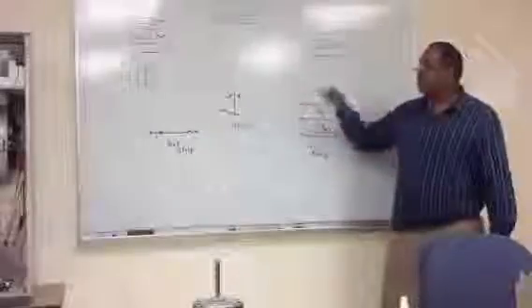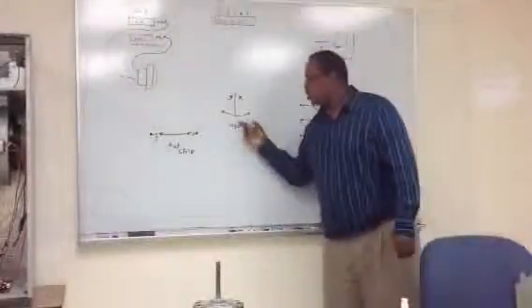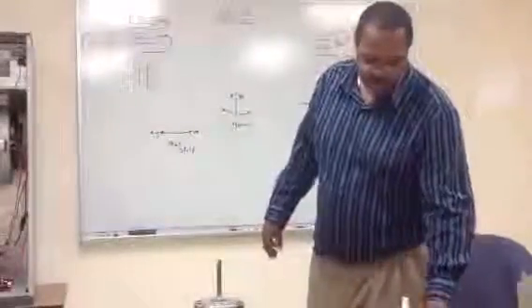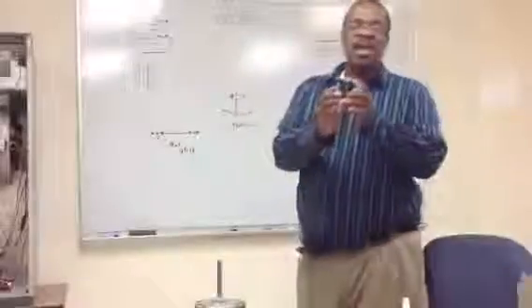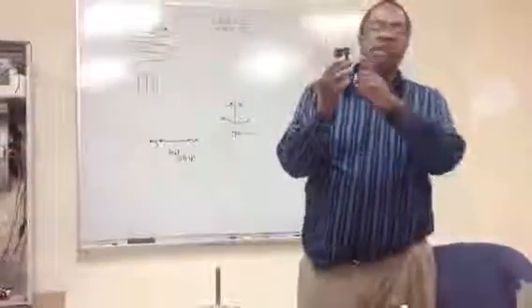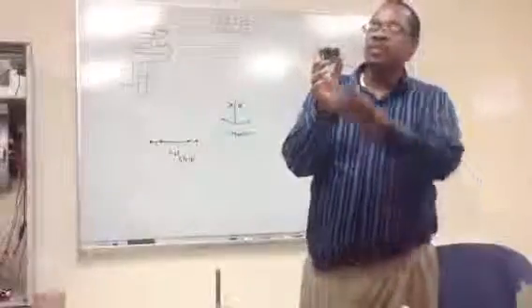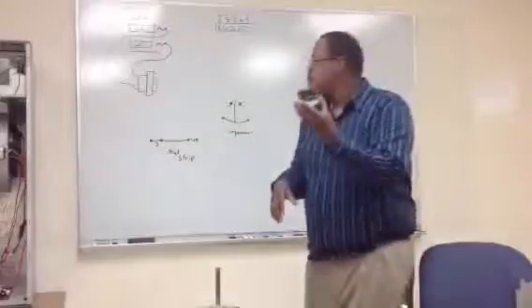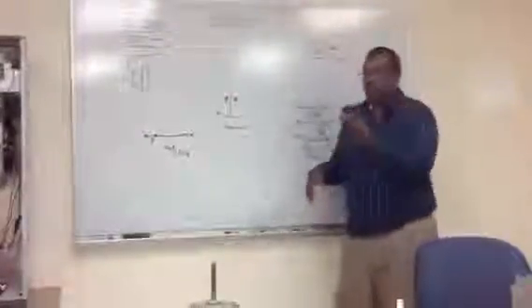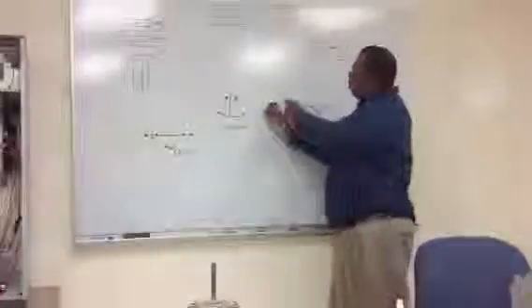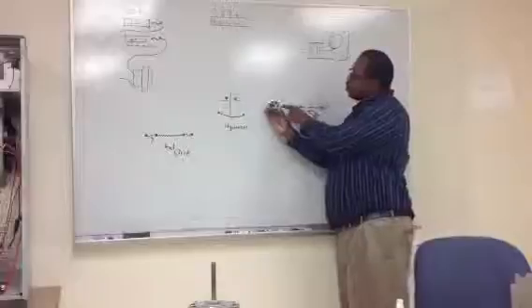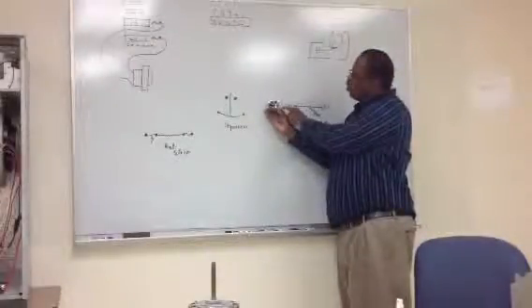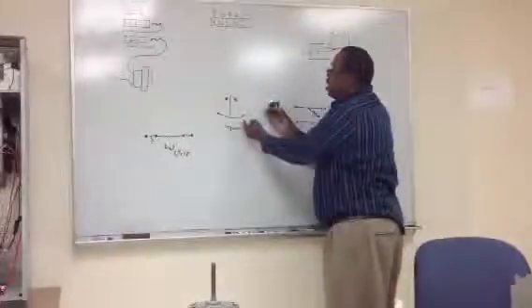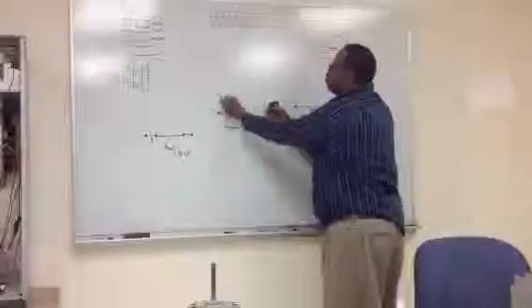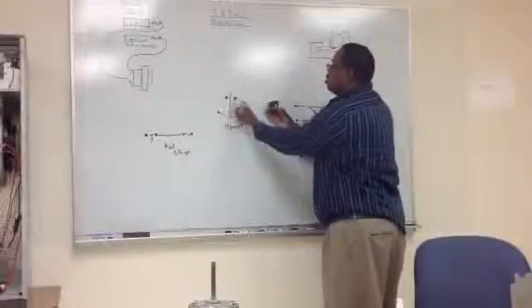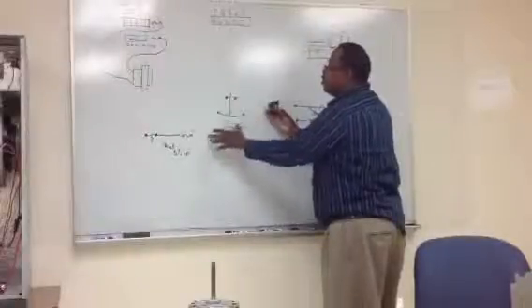So we're going to talk about how these things control. But first, let's start by looking at the sequencer. Now, that is just a pictorial drawing of a sequencer, but here's an actual packaged sequencer. Sometimes they come in tubes, you can get them individually, but if you look at this packaged sequencer, it's got several different circuits. I'm going to pull back over here towards the board. This sequencer has one circuit up top, another circuit in the middle, and then at the bottom it has another circuit. The low voltage is always at the bottom. I only put one circuit on this for this drawing, but it could have another one. Each one of these circuits can control a different heat strip.